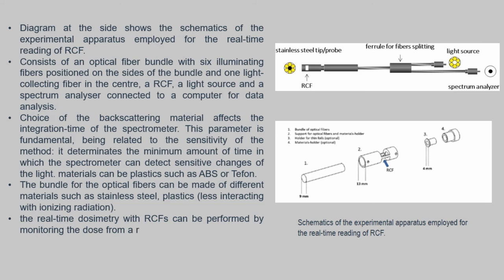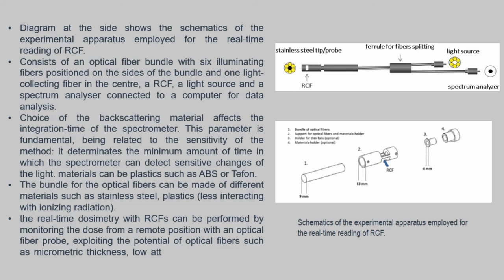The real-time dosimetry of the RCF can be performed by monitoring the dose from a remote position with an optical fiber probe, exploiting the potential of optical fibers such as micrometric thickness, low attenuation coefficient, and low interaction with electromagnetic fields.